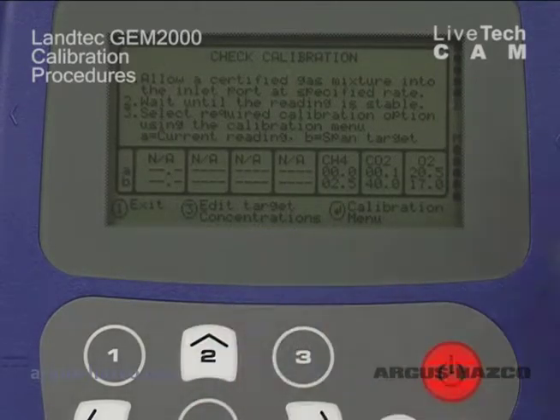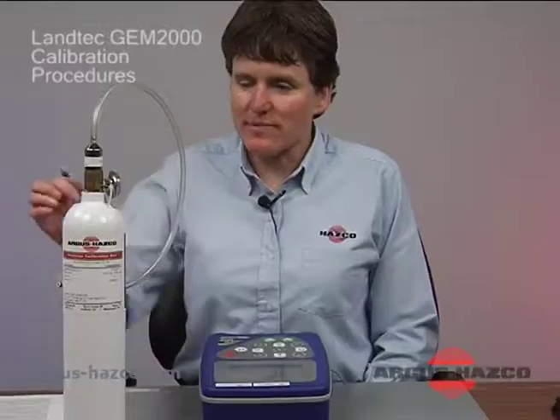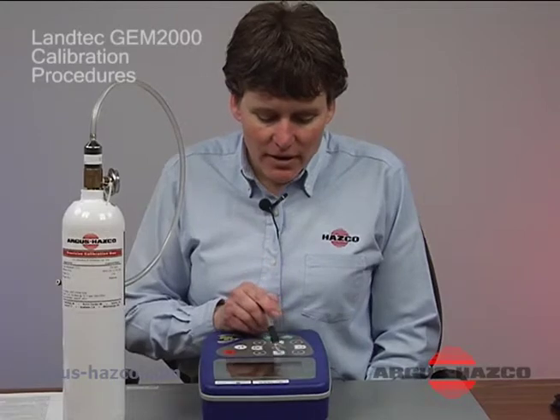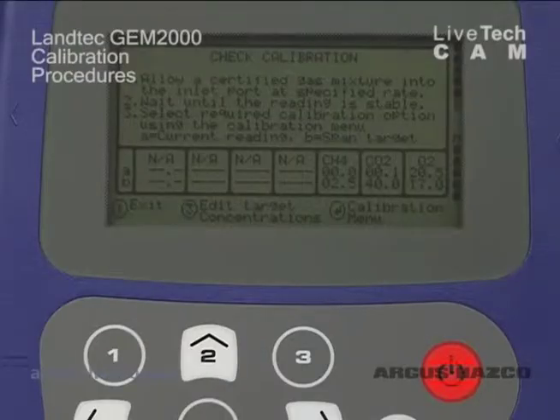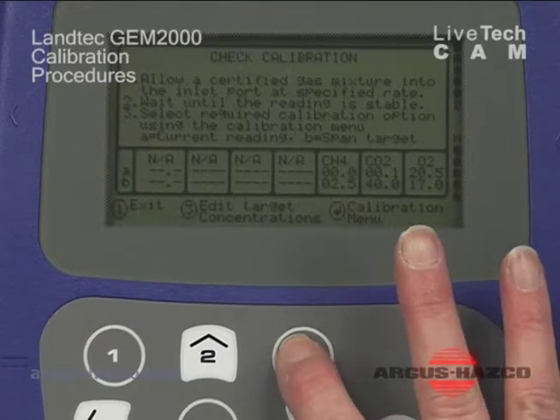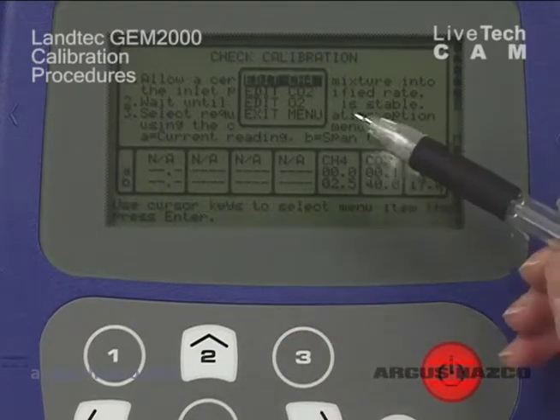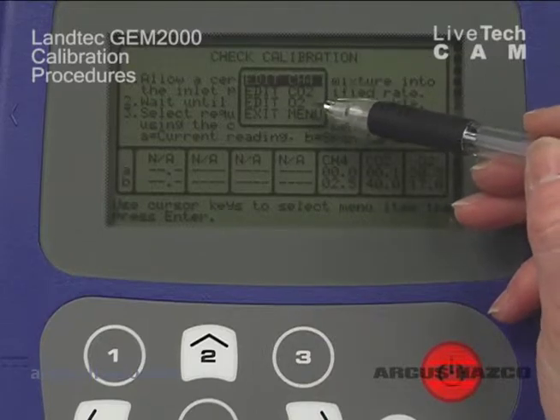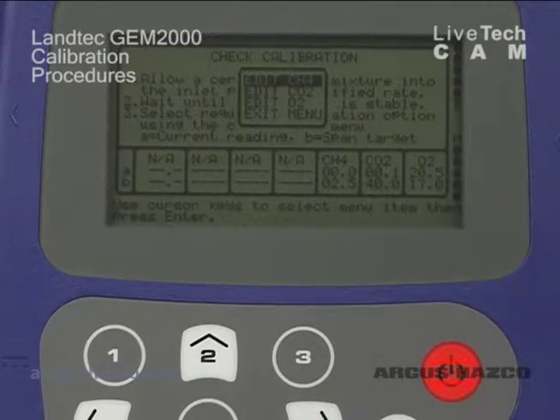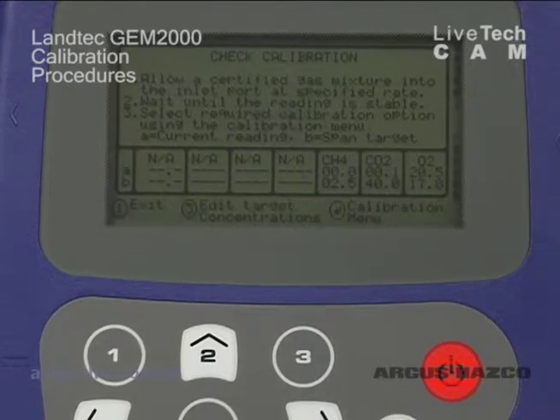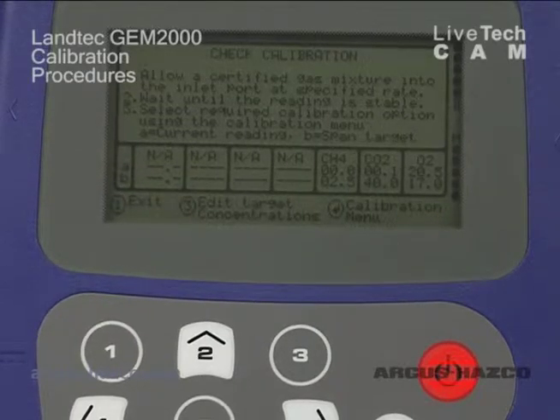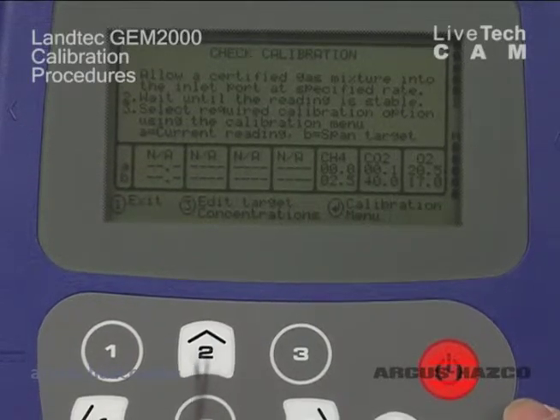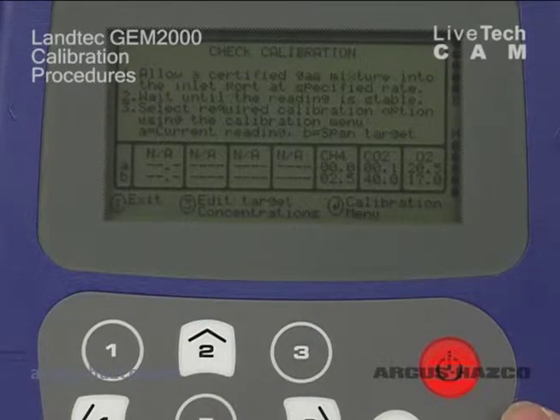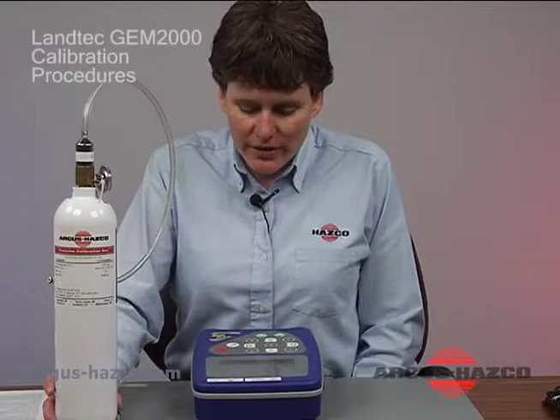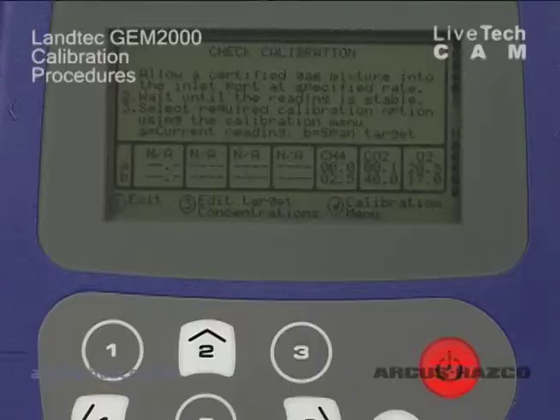What we want to do is, if you need to change these settings to match your calibration cylinder, you would hit number 3, Edit Target Concentrations. And if I hit number 3, then another little submenu pops up, and then I would select what I wanted to edit. And at this point in time, I want to go ahead and just exit out of here. I'll leave my values the way they are. Then next, after our span values are set, we want to go ahead and calibrate the unit.